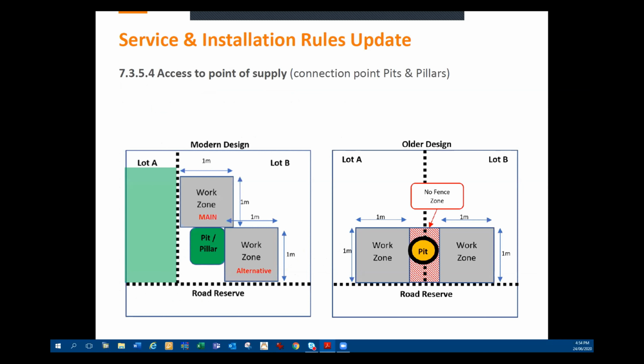electricians and also customers understand what the requirements are, basically for a work zone around a pit or pillar. So there's the primary work zone of 1 metre by 1 metre. If it's a green pillar, the fuse panel within that pillar faces back into the property, so that's the standard work zone. We can have an alternative zone to either side of that pillar, depending on its orientation within the property.